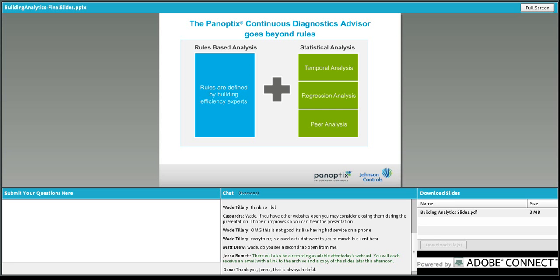Temporal analysis relates equipment performance to time and frequency simultaneously. This involves identifying how a piece of equipment should operate based on past performance, then bucketing that performance into typical behavior for a given time period. If the equipment operates outside of the typical performance for that period, a fault is triggered. A simple example is looking at zone temperatures over time—there will be patterns relative to set points, and if those patterns start to deviate, a temporal analysis fault may be triggered by these powerful analytics.